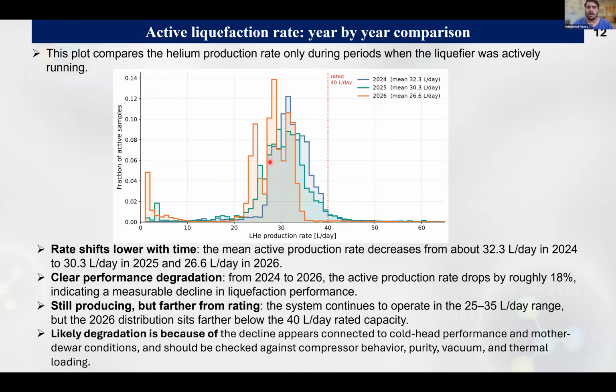We can see how our production rate is consistent, from 26 to 33 over 2024 to 2026. The higher capacity for our system is 40 liters per day. The degradation we see from 2024 to 26 is due to several factors, like the cold head and the cryocooler's performance. One of the cryocoolers is faulty and not working well due to the heat load in the room, so we are working on installing an HVAC system to address that, along with the HP compressor and the purity of the purifier. These are the major degradation factors in our lab.